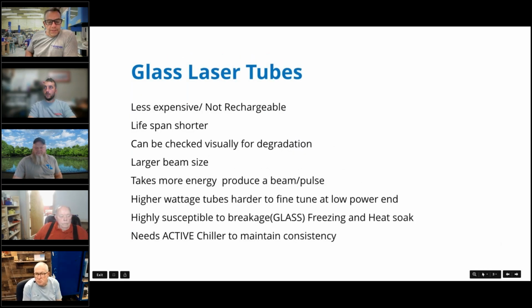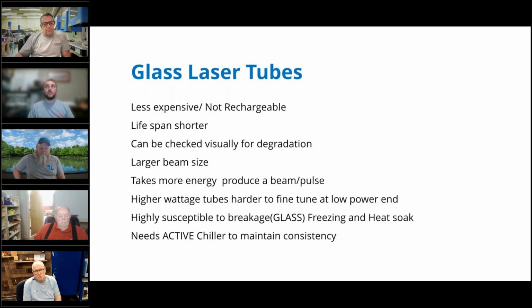Sure. So the interesting thing, and I want to make this real clear because there's a few companies out there that are saying this, and it's not true. You can have a water reservoir, a fan, and a radiator. That does not make it an active chiller. It is trying to cool the water, but the water is going to heat up. And the issue with that, if it's not an active chiller and not actively chilling the water and keeping it at a constant temperature, you can pause your machine, go have lunch, come back and start a job over again, and you're going to have probably double the amount of power because of heat soak. So an active chiller is very important when it comes to these glass tubes, or at least a non-active chiller that can keep up with the tube.